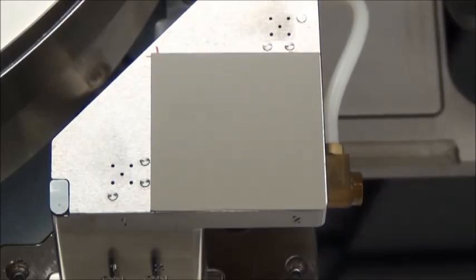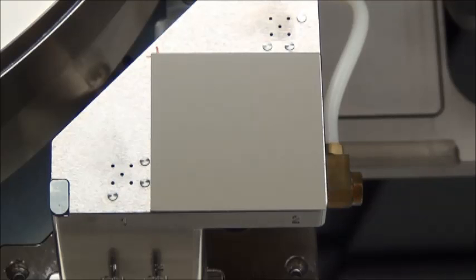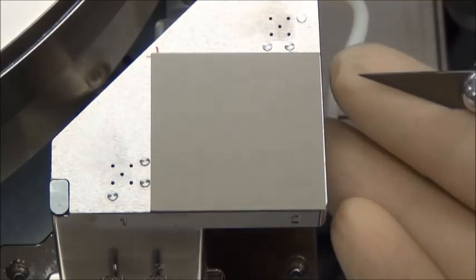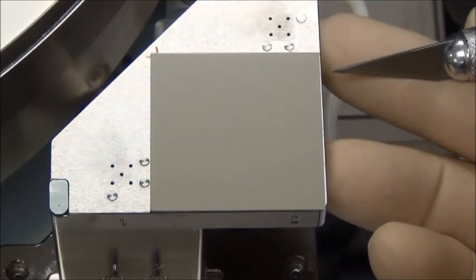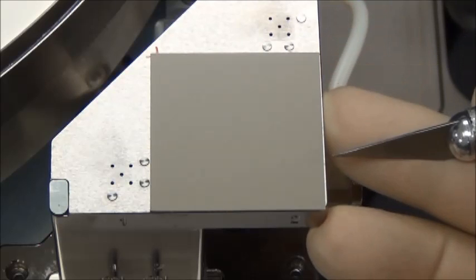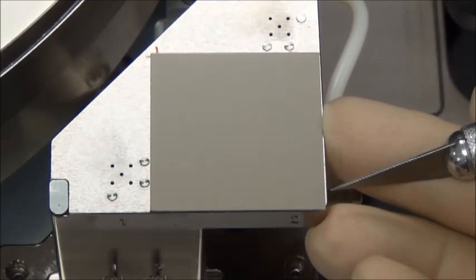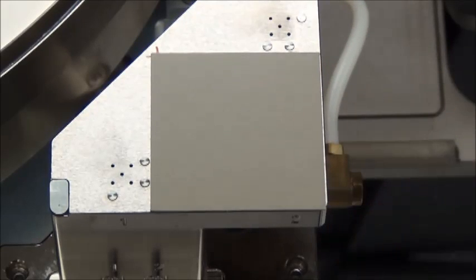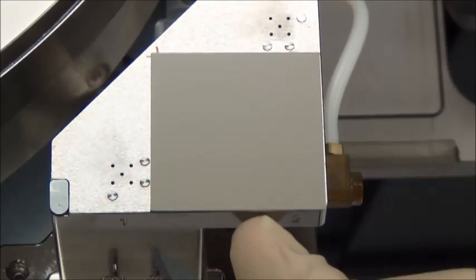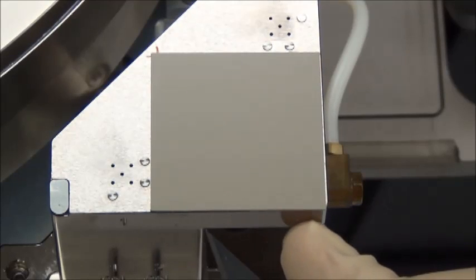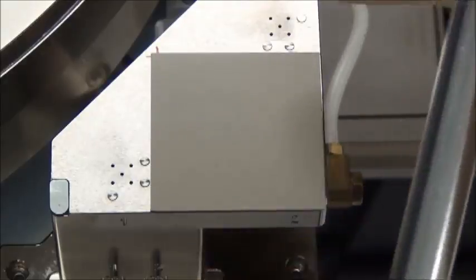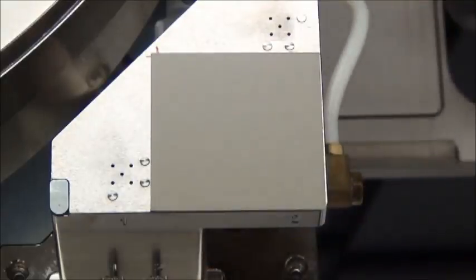When installing an adhesive pad onto the aux chuck surface, it can sometimes be difficult to get the pad edges precisely aligned to the edges of the chuck. If there is a large registration error, you may want to entirely replace the pad and try again. But for small errors, you can simply adjust the position of the fences when setting up pad boundaries later.